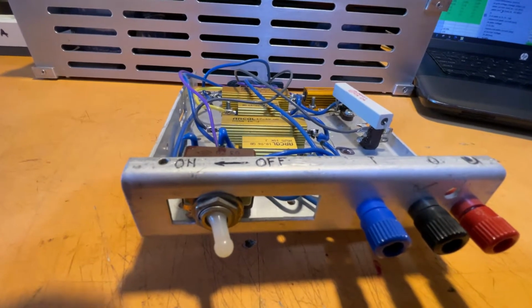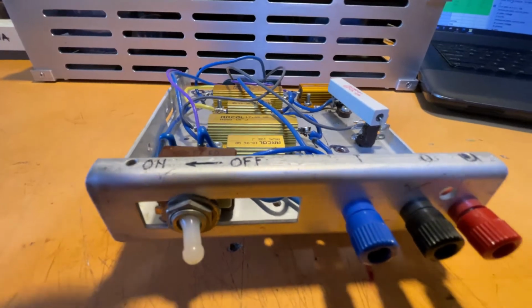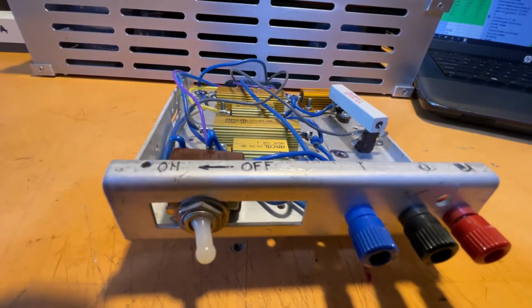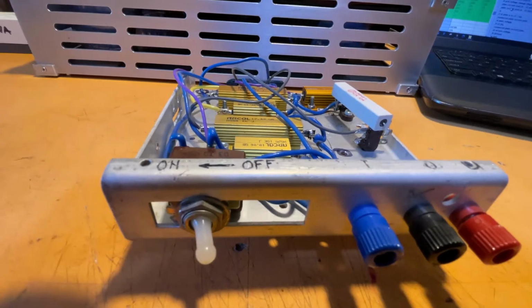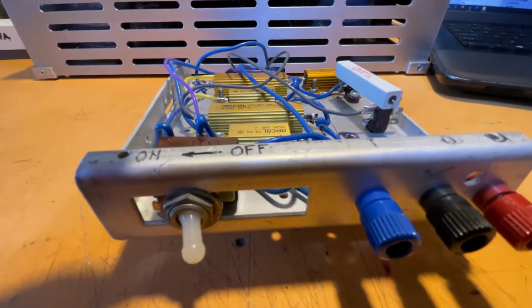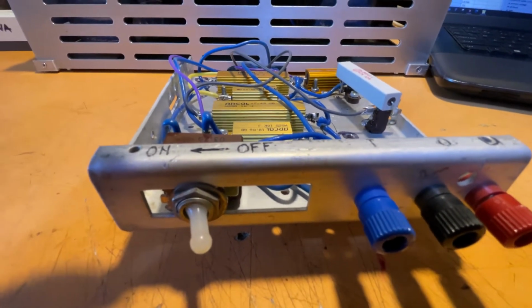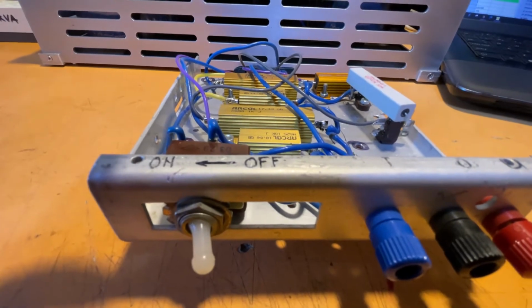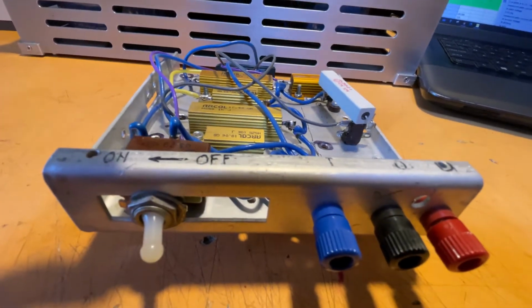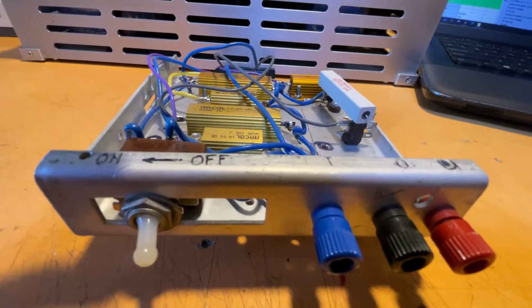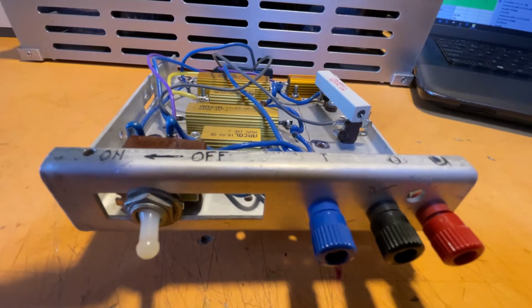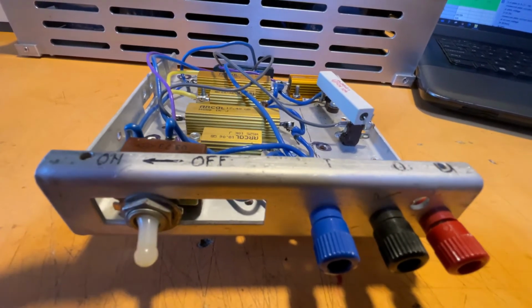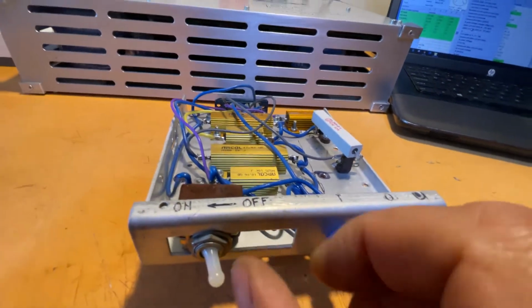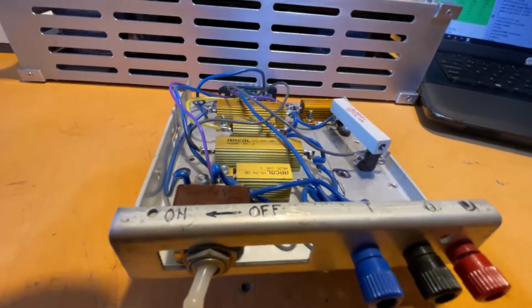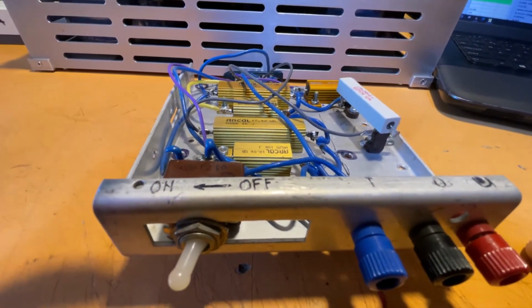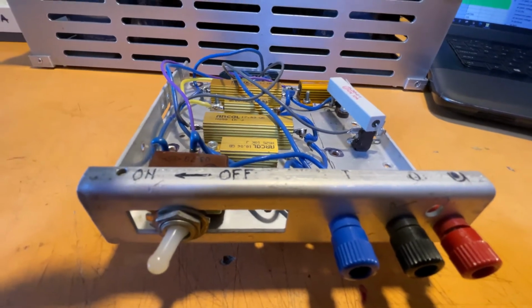As you know, when we supply a bigger tube, 1, 2, 3, 4 amps for filament, on the lines of the circuit that supply the heater, some voltage will drop. So at the tube socket and on the tube pins, we will not have the same voltage as it is supplied from the device. So moving this switch to this position, we set the compensation that the device will make on filament voltage.